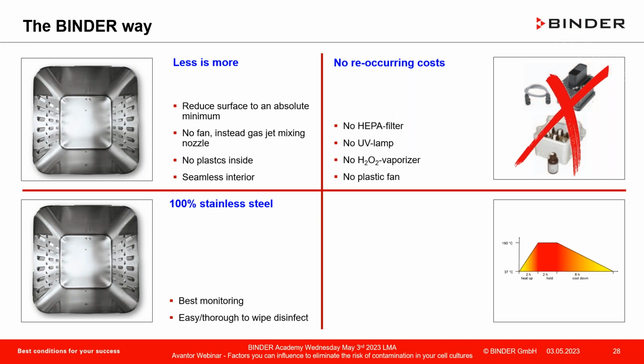That's a philosophy we decided, Mr. Binder decided many years back, many centuries back actually, that we're on the stainless steel side of life, and that's the only possibility, that's the only form for an interior chamber we offer. And you have 180 degrees C in 11 hours, which means from 37 degrees incubation temperature rises over 2 hours to 180, remains there for 2 hours, and then slowly descends down over a period of 6-7 hours.